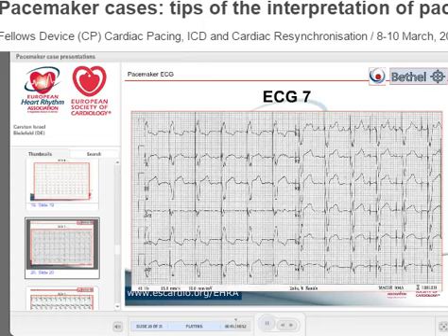So this is just an example. Go through intrinsic rhythm, pacemaker behavior, and know all the algorithms. And that would be algorithm number 11. Here is the schematic view. When you see, for a complete timing cycle, sensing all the time, again and again, this sensing is continuous for the device, and it says this is noise, not a biological signal. I'll skip this. It's funny, but a little bit embarrassing.